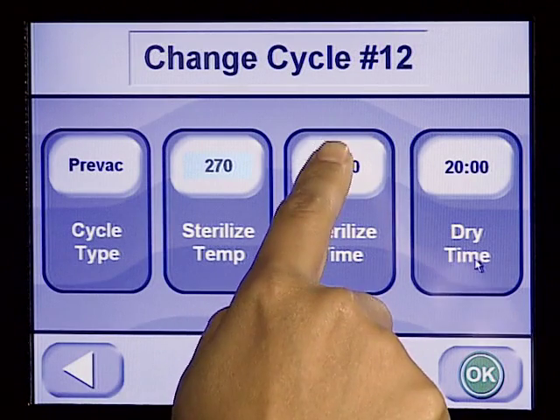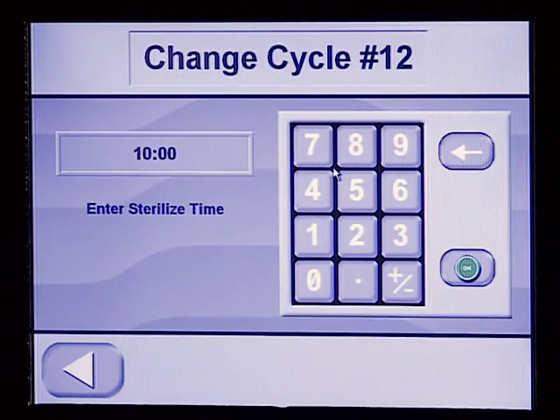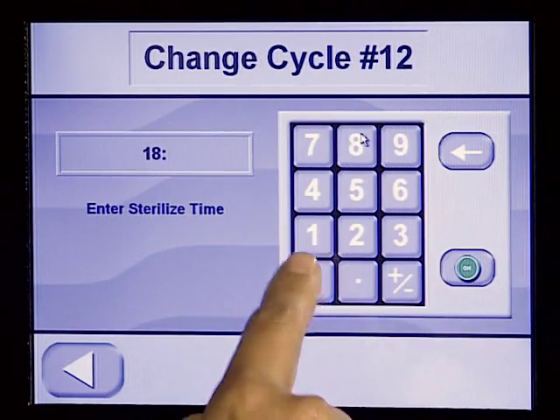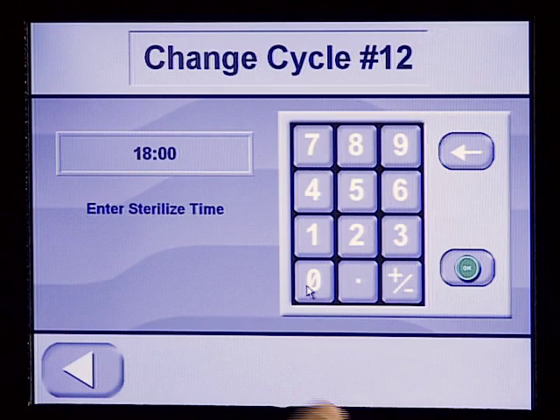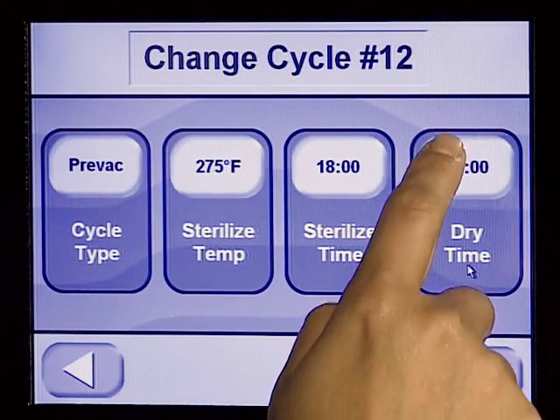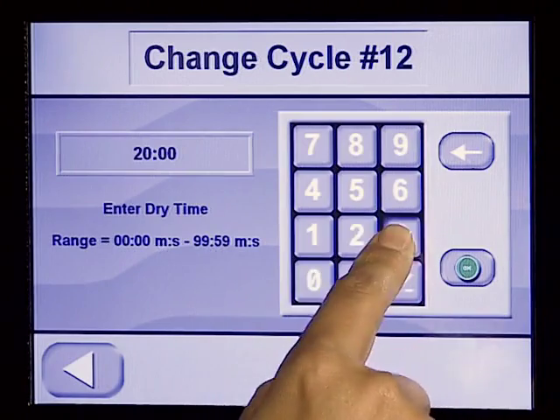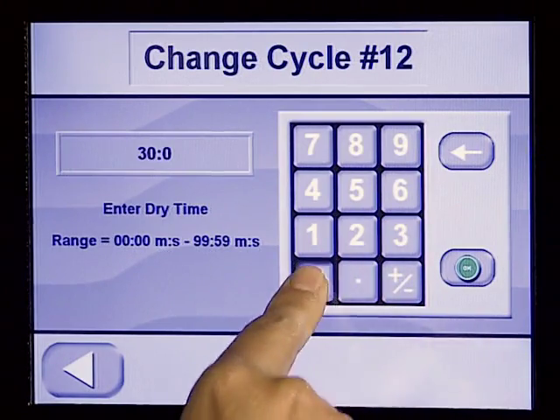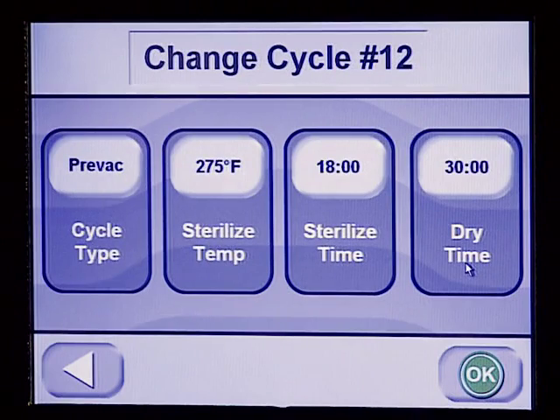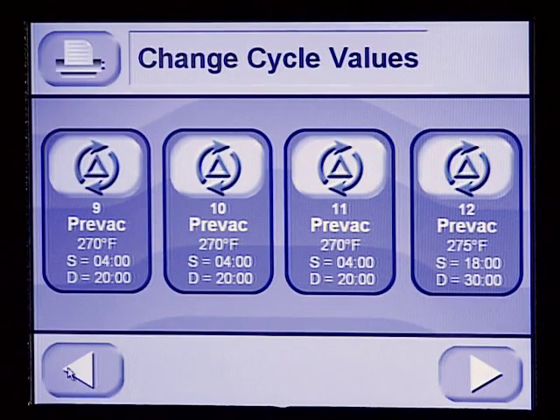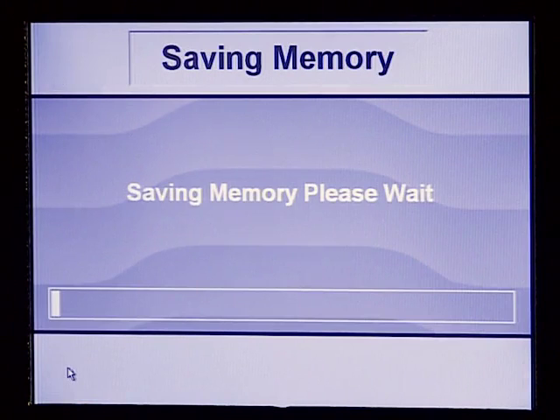To adjust the sterilize time for a 270 degree Fahrenheit pre-vac or SFPP cycle, enter the new value ranging from 4 minutes to 99 minutes and 59 seconds. A 275 degree Fahrenheit pre-vac or SFPP is adjustable from 3 minutes to 99 minutes and 59 seconds. To change the dry time, enter the new value using the same range of 1 minute to 99 minutes and 59 seconds. Press the Exit Screen button to go back to the Options screen.